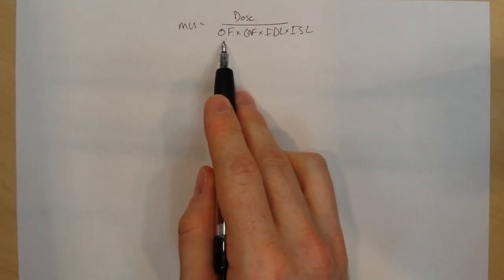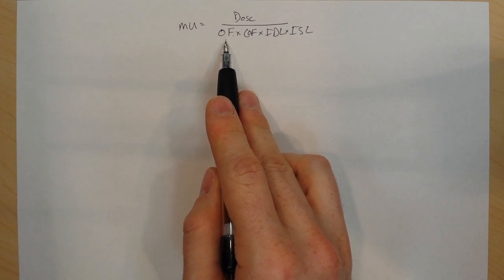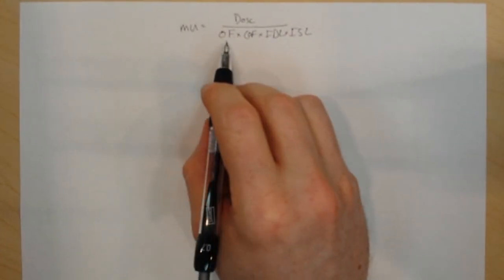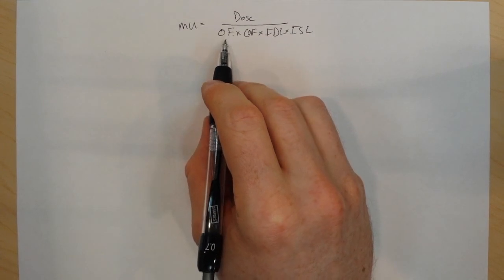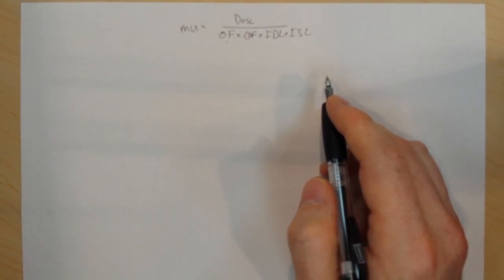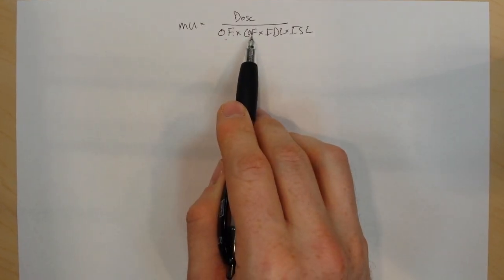So going first with the output factor, on linear accelerators, the machines are hard-coded so that when you insert a particular electron cone into the machine, it automatically dials up a set of field sizes. Those field sizes are hard-coded because the output that you get from the electrons varies dramatically with field size. So instead of the therapist being able to dial up whatever field size they want, the physicist only has to measure one set of output factors per cone because the jaws always go to the same spot. The cutout factor can change.